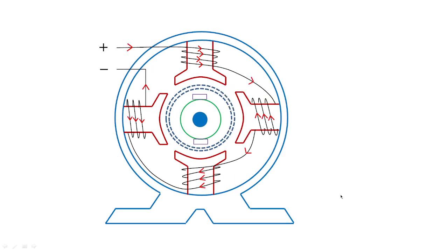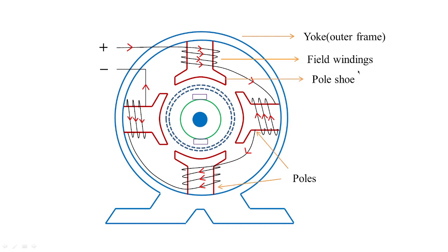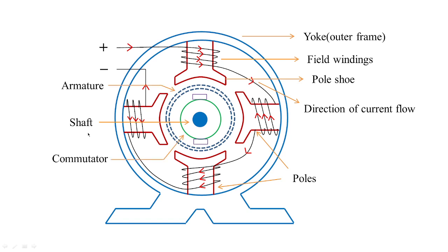We have to keep in mind the construction details: you have a yoke which is the outer frame, you have the field windings which are placed on the poles, the poles are supported by pole shoes such that the windings placed on the poles should not fall on the rotating part of the machine. The rotating part consists of the shaft and the commutator, where the entire machine is supported by brush contacts where you collect the current.